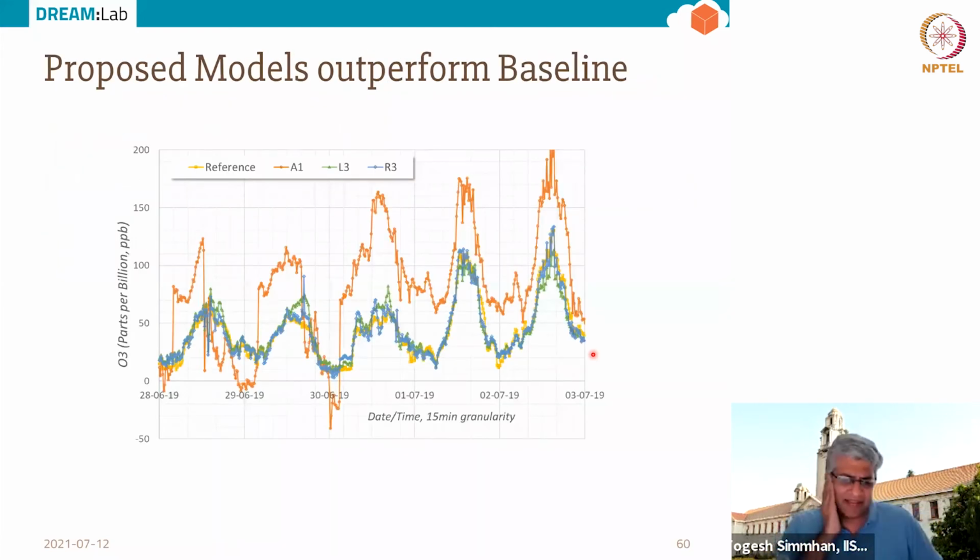So that was the good news. The bad news is that there are challenges in making this reliable across time and across cities. For example, we did deployments in Delhi, Kanpur, and Mumbai at IIT Bombay, and we find that the same calibration model is not good enough for all 3 locations. You have to retrain the model for specific cities because Mumbai has very high humidity, right on the seashore. Delhi has very arid conditions. The IIT Kanpur campus has a very different locale as well. So location-specific retraining and calibration is required.